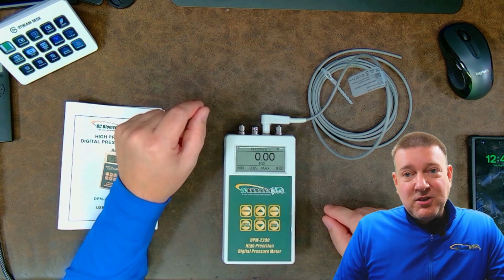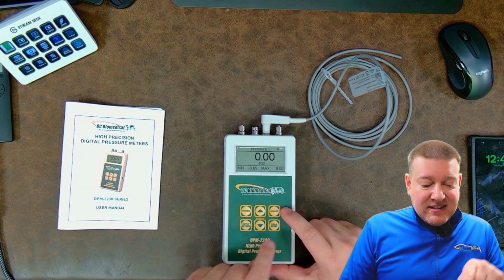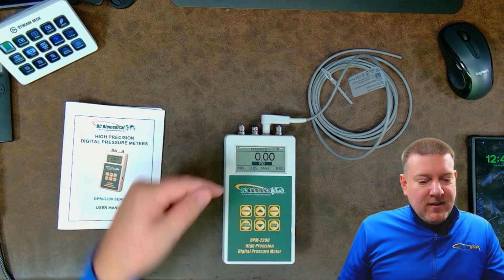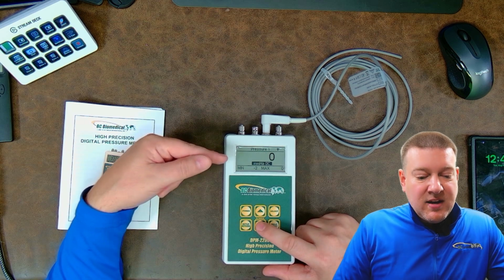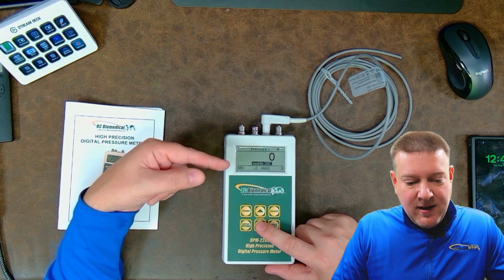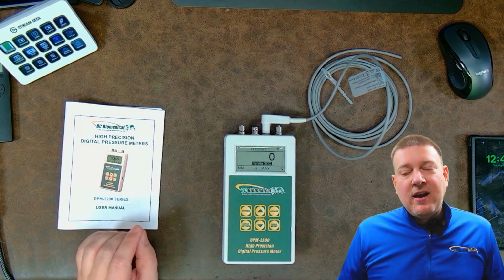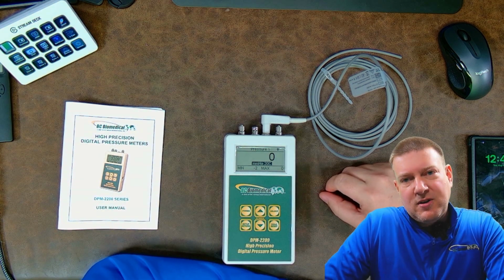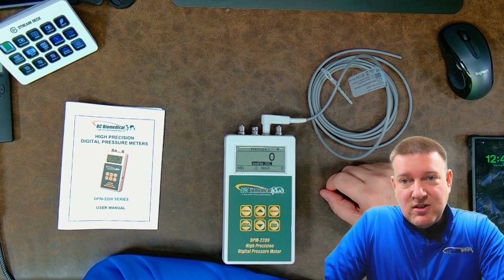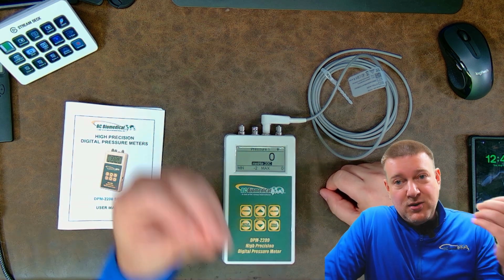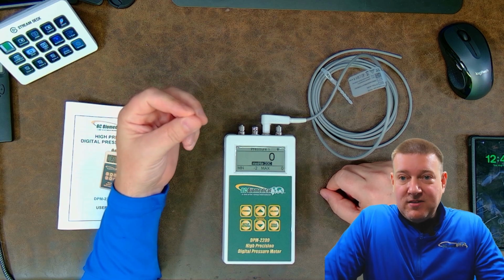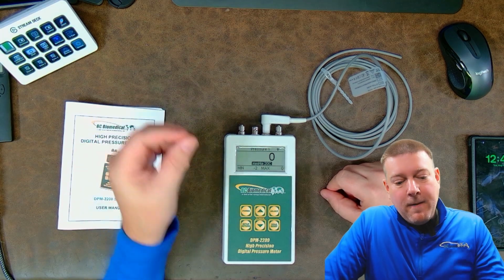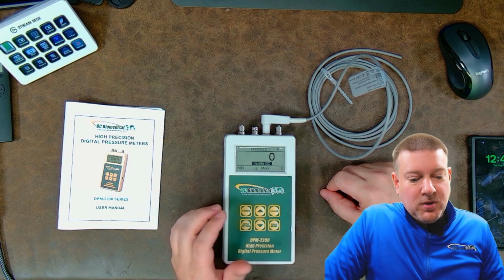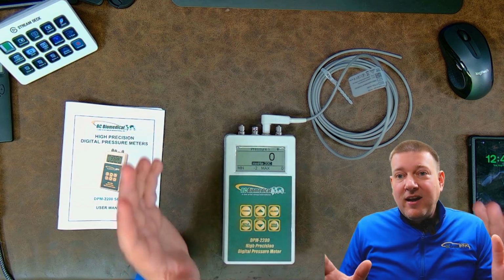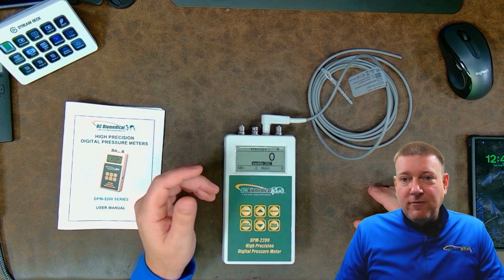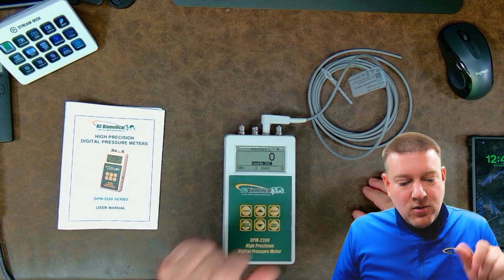Now, both of these measurements I've shown you are in PSI, but that is easy. Hit the select button and it goes to the units field, and we can migrate through all the different ones. I have millimeters of mercury at 0 degrees centigrade and millimeters of mercury at 20 degrees centigrade. Now, why do you think they have two different temperatures? Well, mercury changes its density based on its temperature. At 0 degrees centigrade, it's going to have a higher density, thus it's not going to reflect as accurately on the pressure. And if I go to millimeters of mercury at 20 degrees centigrade, it's going to have a much lower density, and it's going to reflect much looser on your pressure.